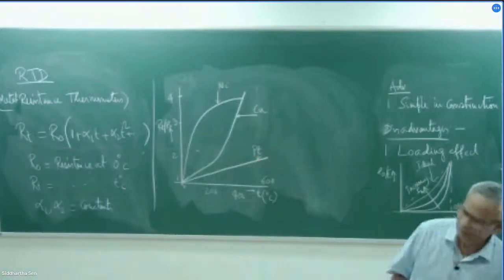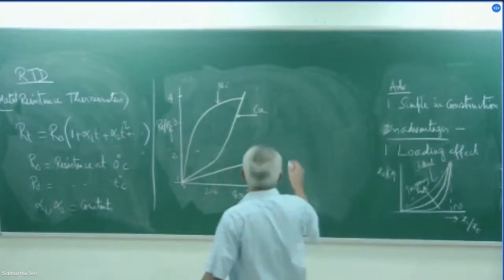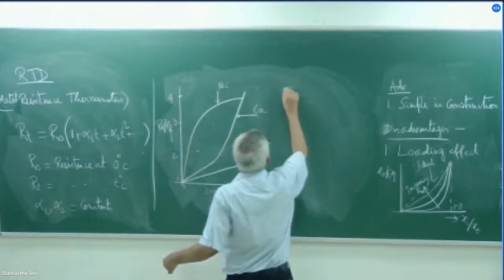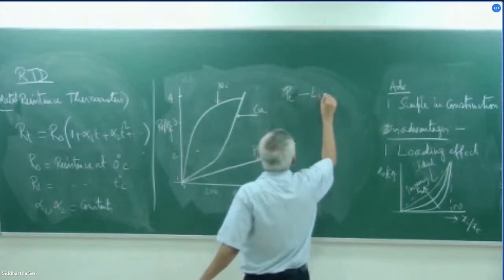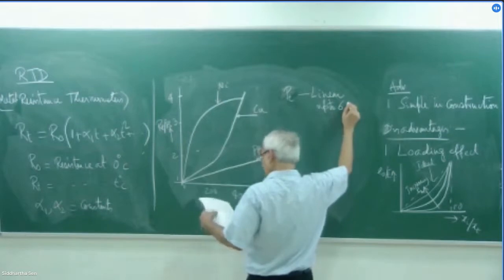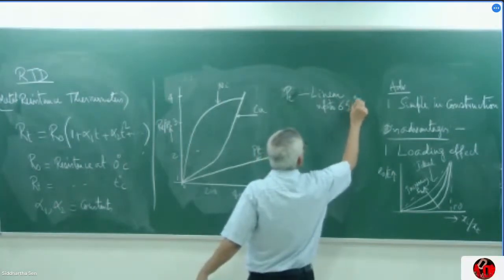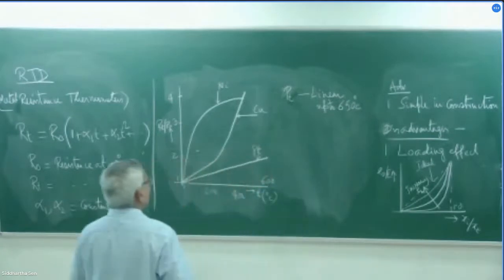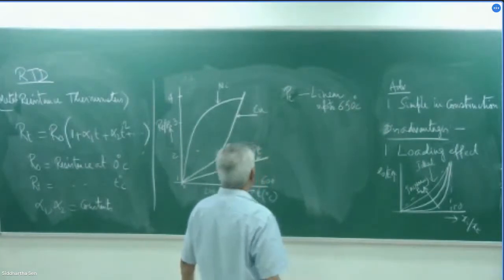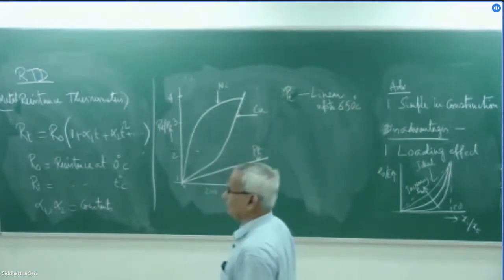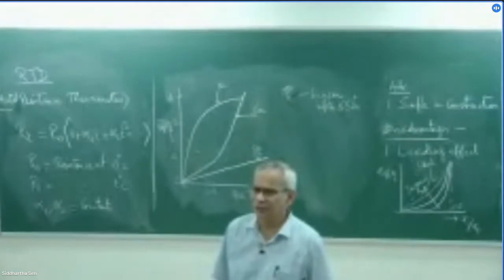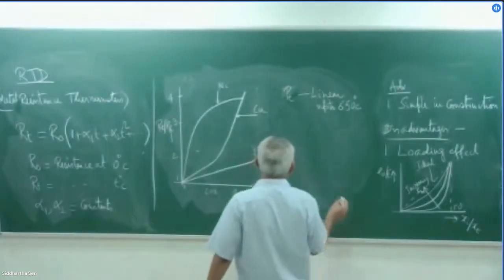In fact, for platinum the sensitivity is less. Platinum is linear up to 650 degrees Celsius and very useful over a wide range, but definitely platinum cost is a little bit higher. So naturally that is the problem there.